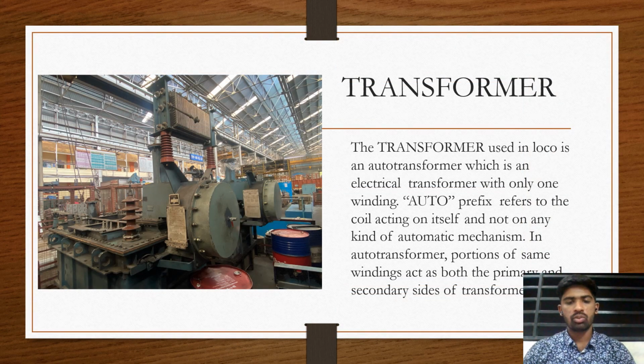In this short video, we'll learn about tap changers that are used particularly in electric locomotives. Inside electric locomotives, the tap changers are placed inside the transformers. The transformers that are used in electric locomotives are called auto transformers, which is an electrical transformer with only one winding. This "auto" does not refer to an automatic mechanism, but to the coil acting on itself. In these types of auto transformers, portions of the same winding can act as both the primary as well as the secondary side of the transformer.